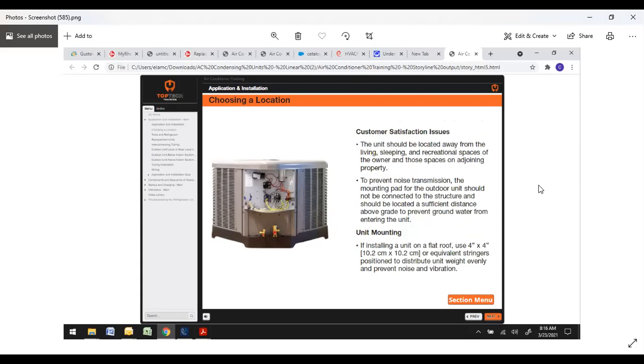Customer satisfaction issues. The unit should be located away from living, sleeping, and recreational spaces for the owner. So you really don't want to put it next to a deck or an outdoor kitchen area. Try to stay away from bedrooms as best you can. To prevent noise transmission, the mounting pad for the outdoor unit should not be connected to the structure and should be located a sufficient distance above grade to prevent groundwater from entering the unit. If you are installing a unit on a flat roof, we don't see a whole lot in our region, but if you do, use 4x4x4 or equivalent stringers positioned to distribute the weight evenly and prevent noise and vibration.